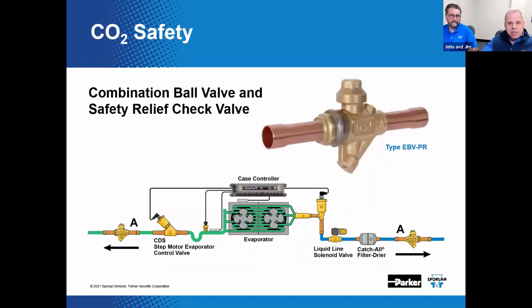This is slide 22. Sporlan manufactures a combination ball valve and safety relief valve. I'm avoiding much in the way of commercialization during the course of this, but I thought I would mention this. Notice the orientation of the two valves positioned around the evaporator. I guess they're talking about this right here. Yep. And look at how that valve is positioned and look at how that valve is positioned. So, right. So with those, it would not allow liquid refrigerant to be trapped in there and potentially create an overpressure situation. Wow. Good deal.